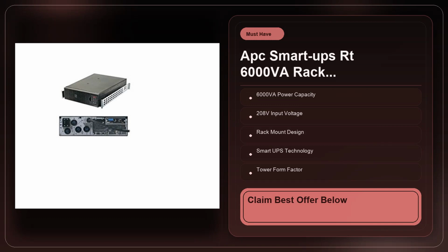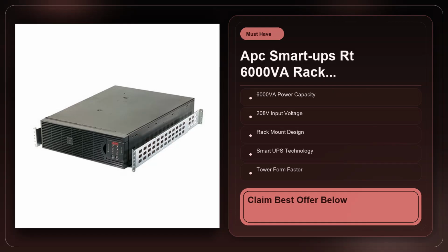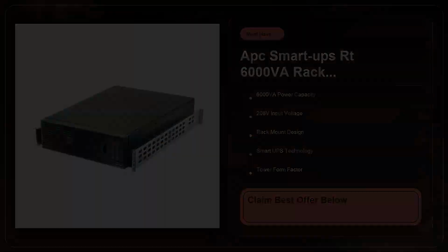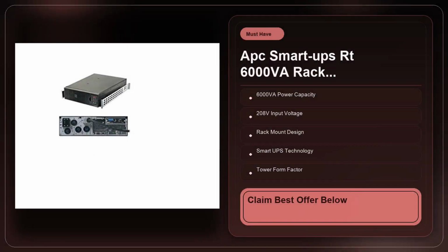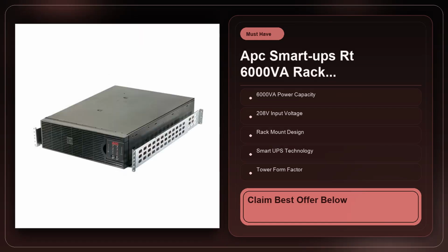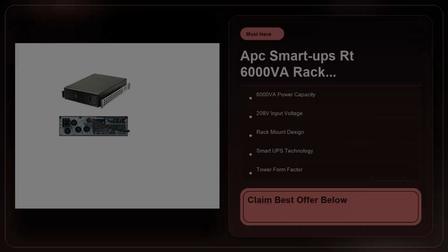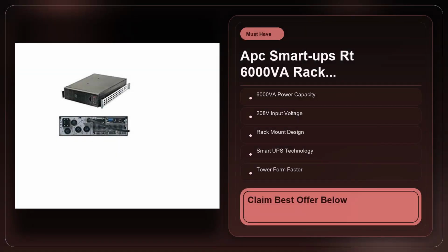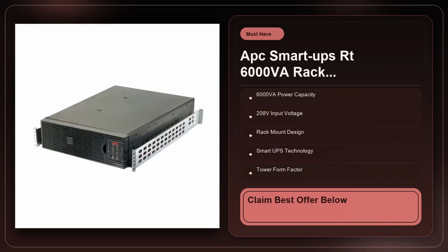What makes the APC Smart UPS RT6000 VA worth a closer look is that it sits right in the sweet spot for medium-tonnage rack deployments that run on 208V 3-phase power. It's not a tiny desk-side backup, and it isn't a massive industrial unit meant for whole building protection. Instead, it's designed for businesses that need to keep several rack-mount servers, a core switch, and perhaps a SAN enclosure alive for the 15 or so minutes it typically takes to transition to a generator or gracefully shut down.